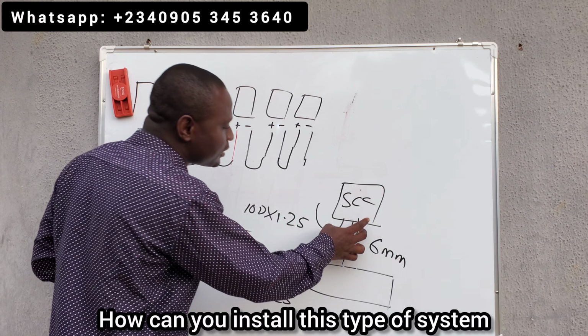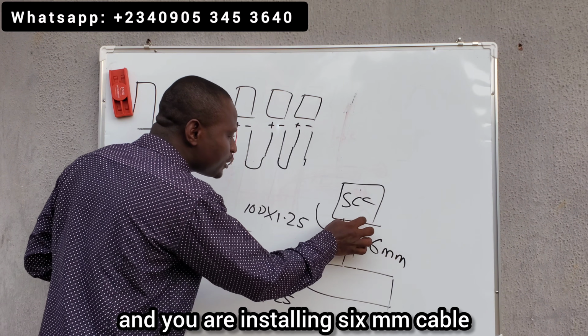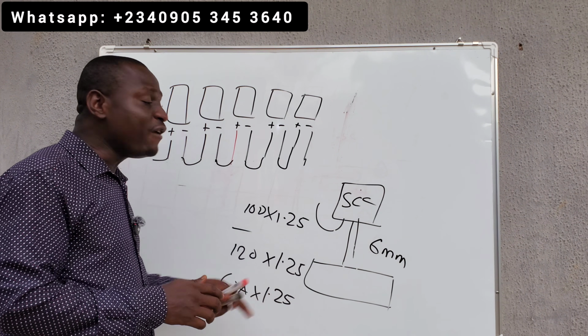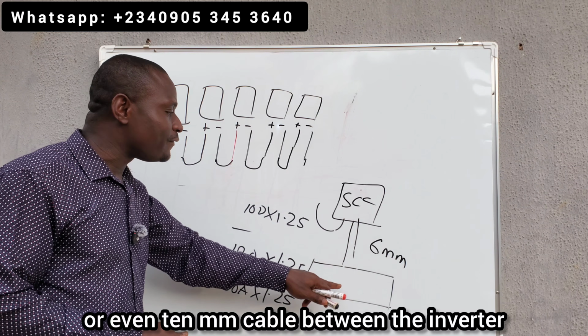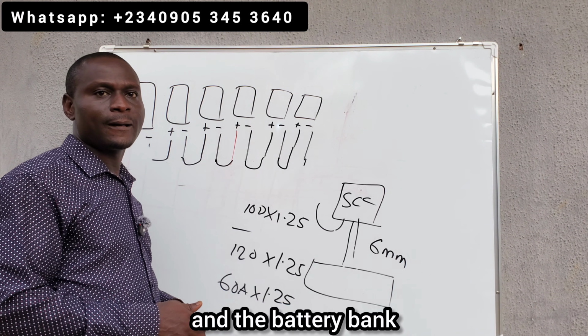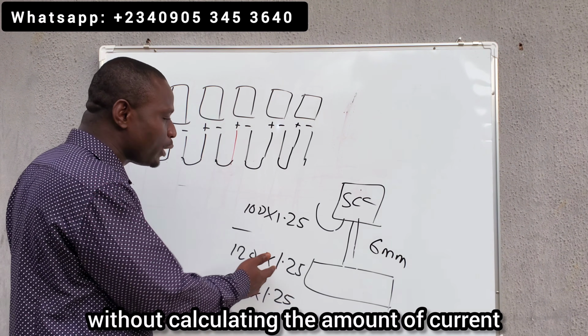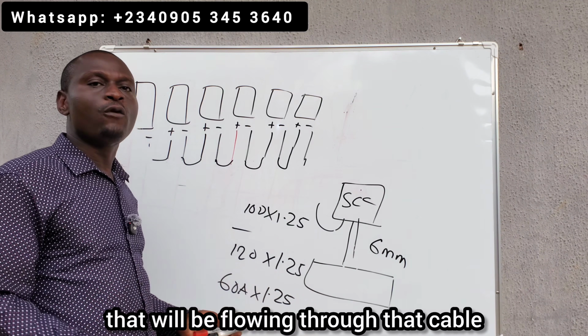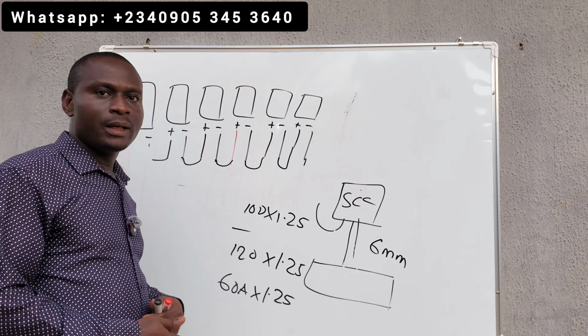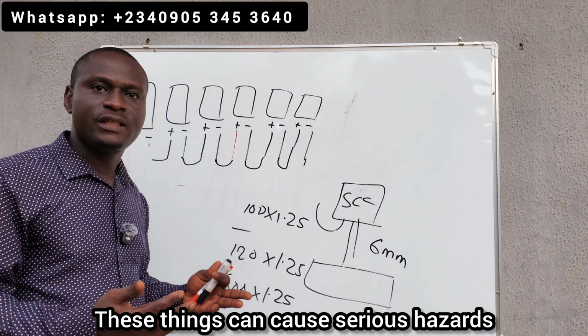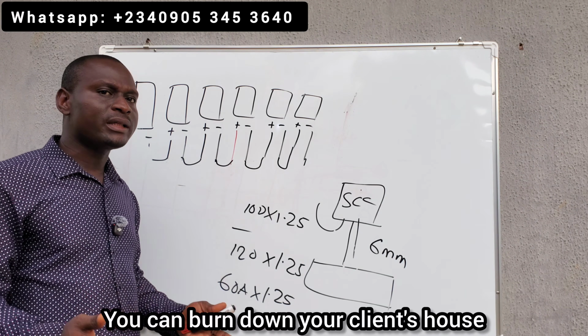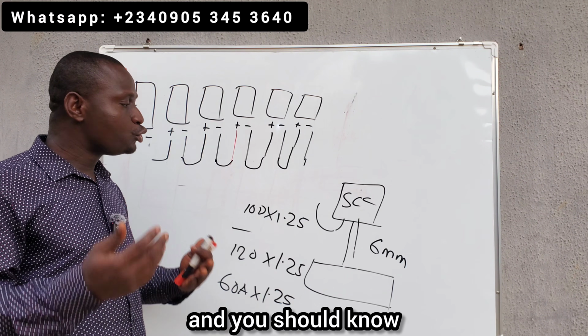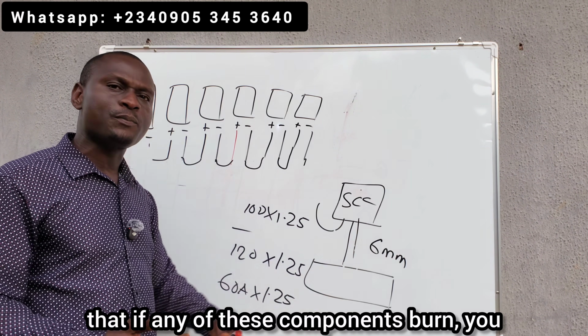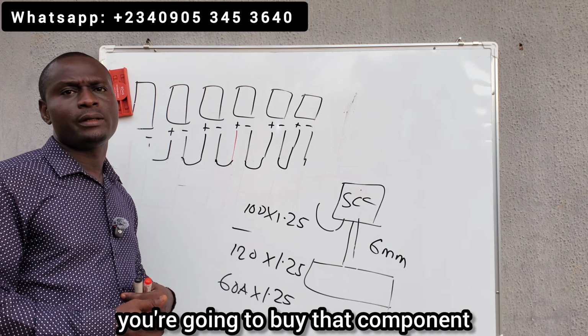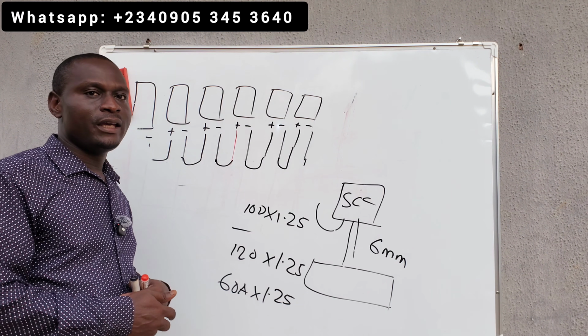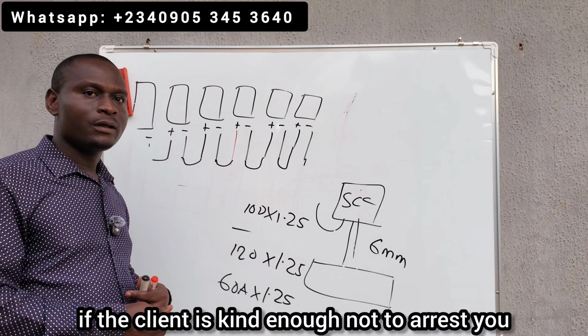How can you install this type of system and use 6 mm or even 10 mm cable between the inverter and the battery bank without calculating the amount of current that will flow through that cable? These things can cause serious hazards — you can burn down your client's house. And you should know that if any of these components burn, you're going to buy that component and replace it, if the client is kind enough not to arrest you.